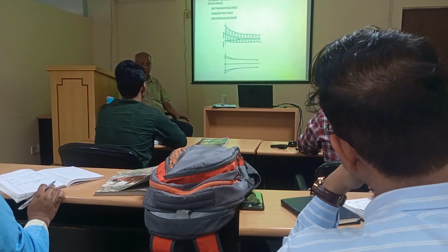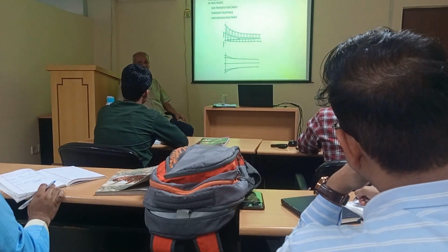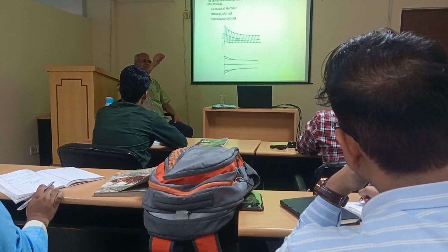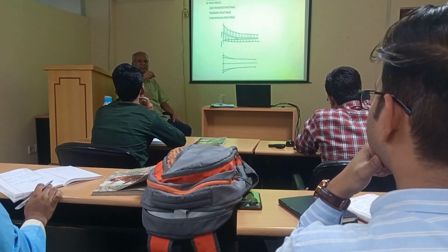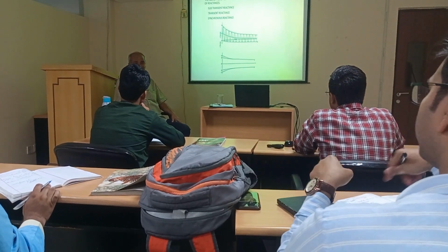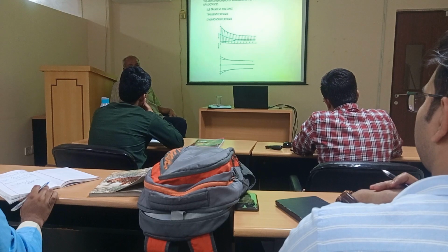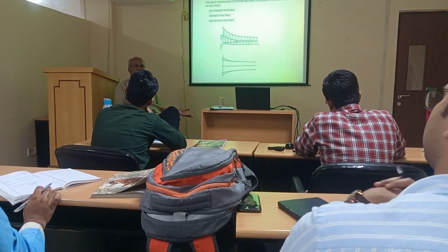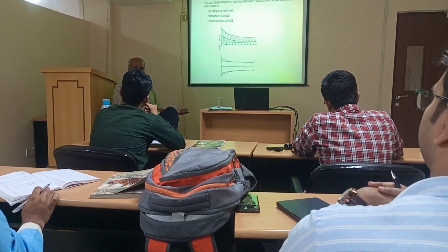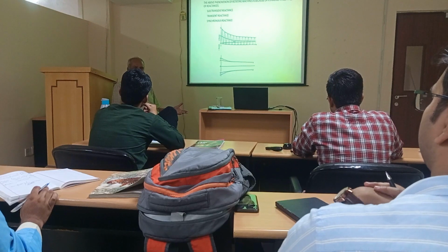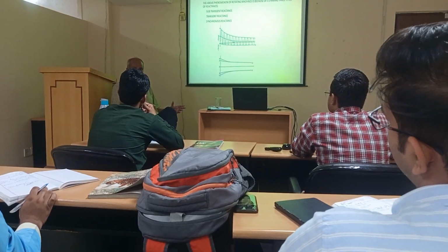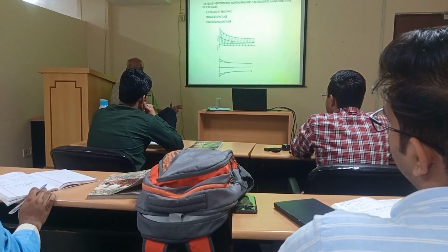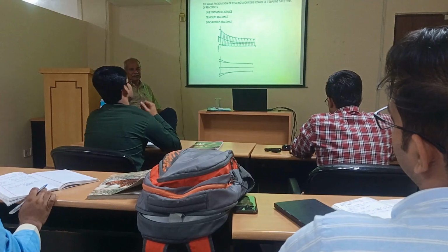Based on this, these machines are rated on the nameplate and technical sheet: subtransient reactance is this much, transient reactance is this much, synchronous reactance is this much. They got these values by doing this calculation in the test bed, as you do for transformers. For generators you do not have access like that, so you do not know. But in the transformer college laboratory, you must have done the load loss and no load loss tests, and based on that calculated the reactance.